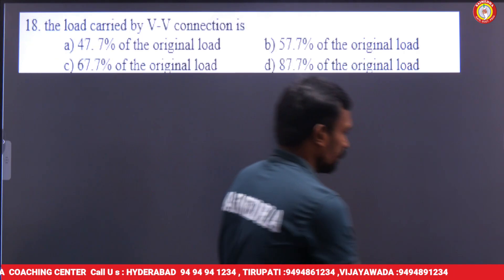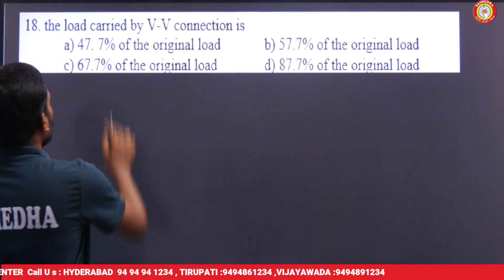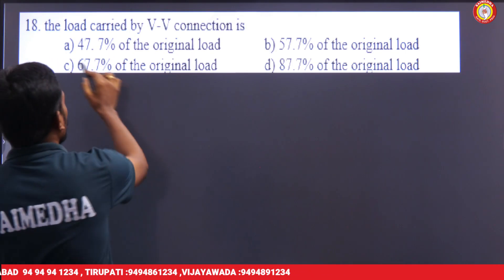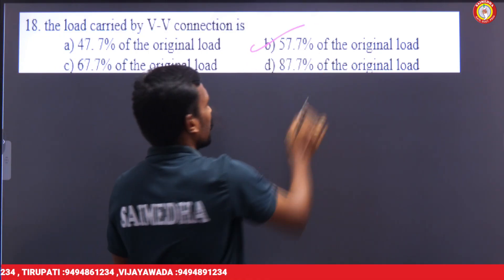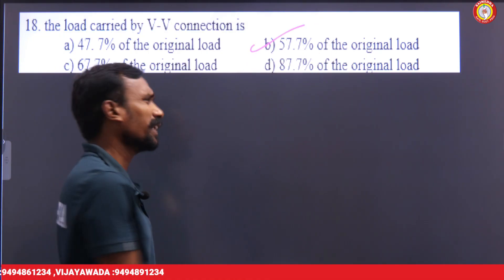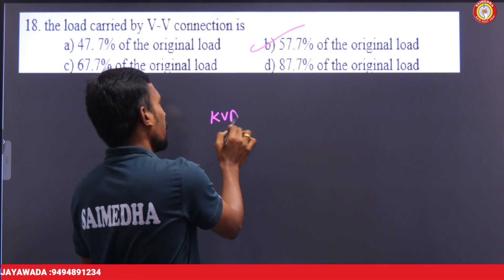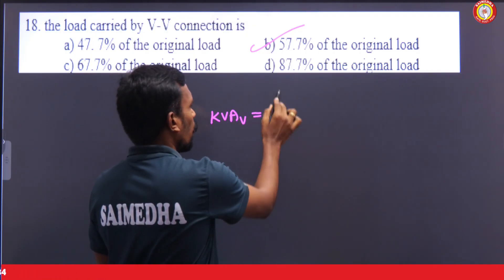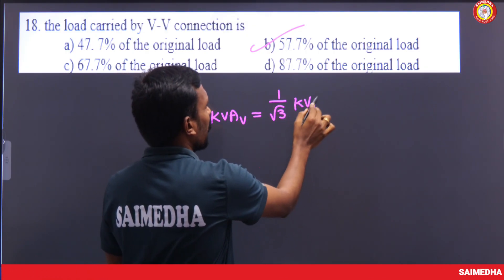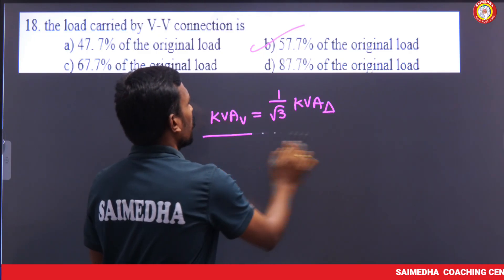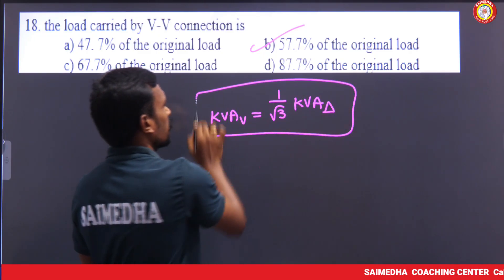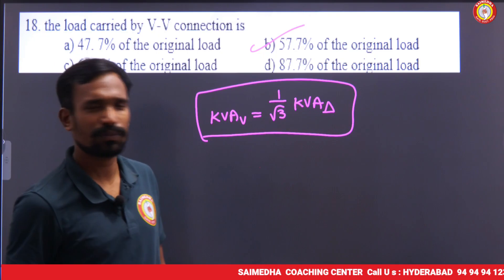The load carried by an open delta connection: the KVA of open delta equals 1 by root 3 times the KVA of the full delta, which is 57.7% of the original load.